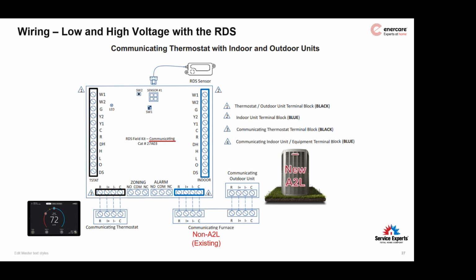With this, as you can see, this one has a single sensor showing on it. As far as I know, all the external boards from Lennox and ADP are going to come with 2 sensor ports. So you'll actually see a second sensor port sitting right here, even though it's not drawn here. You can see the thermostat connections are going to be on the black connection. And then the indoor connections will be the blue connectors on that board. This is pretty straightforward. Are there any thoughts or questions around this stuff? Again, Lennox specific, they have their own communicating version of this RDS board for pairing a new A2L system with a legacy furnace or air handler.